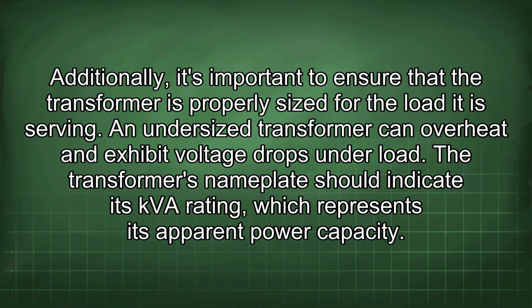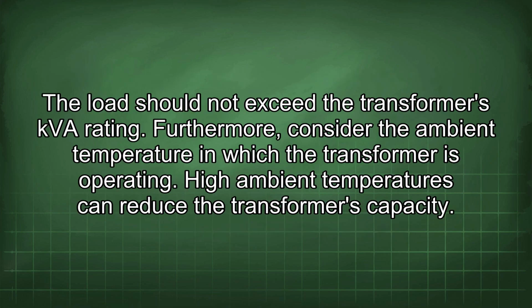Additionally, it's important to ensure that the transformer is properly sized for the load it is serving. An undersized transformer can overheat and exhibit voltage drops under load. The transformer's nameplate should indicate its kVA rating, which represents its apparent power capacity. The load should not exceed the transformer's kVA rating.